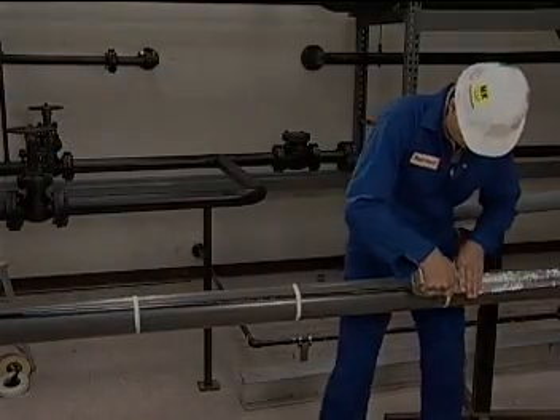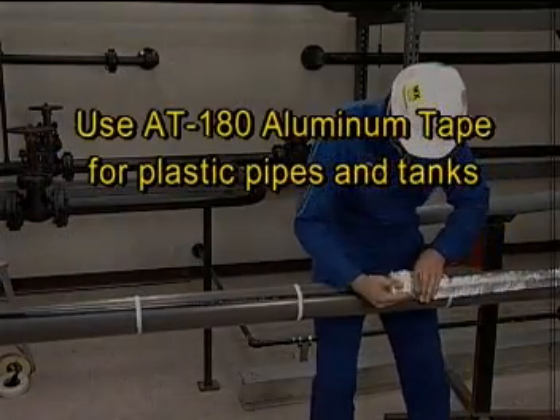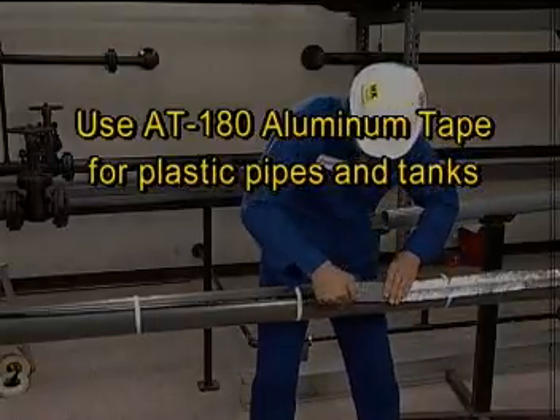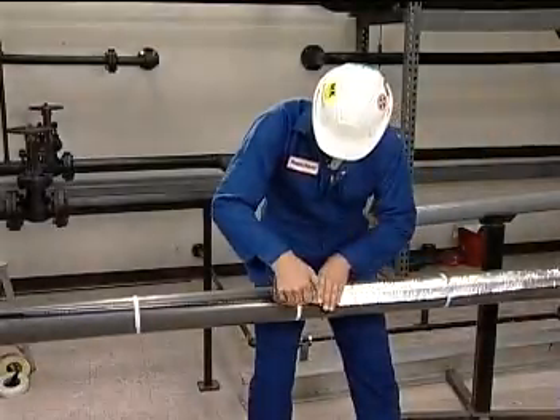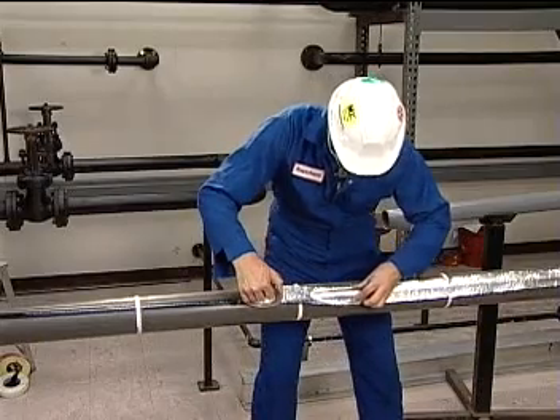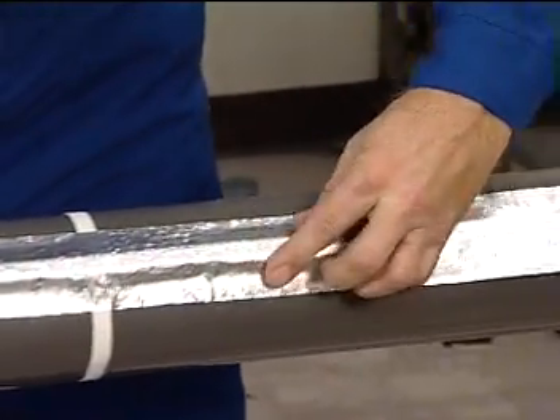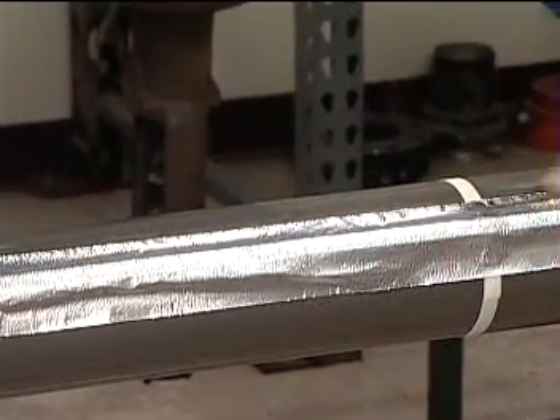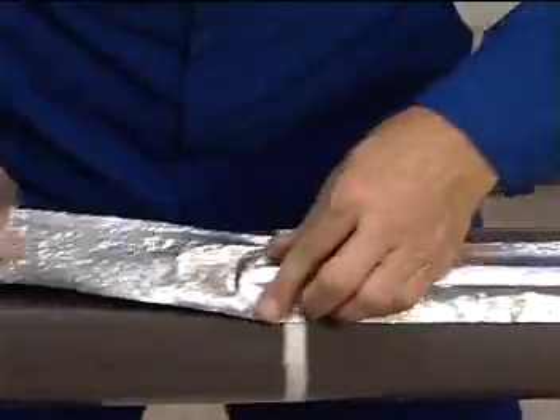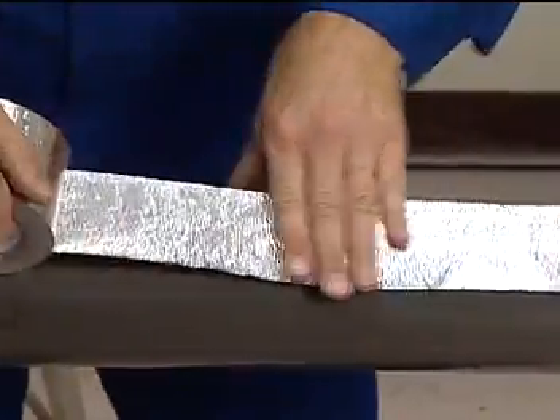Use AT180 aluminum tape for plastic pipes and tanks. Install the AT180 tape in one continuous run over the heating cable. Do not ever use masking tape, electrician's tape, metal bands, or wire to attach the cable. They may not have the proper temperature rating, and they could damage the cable and cause a short.